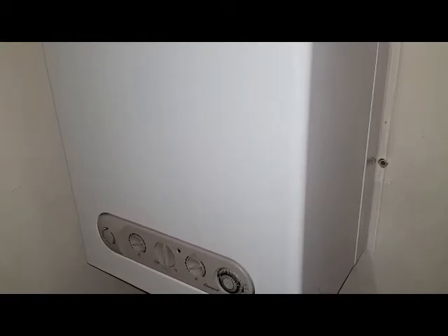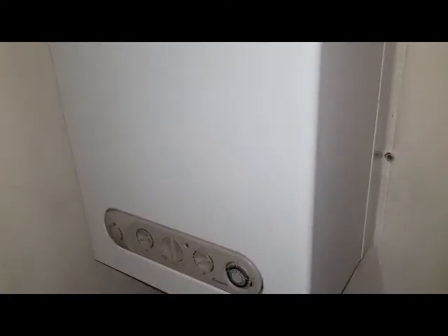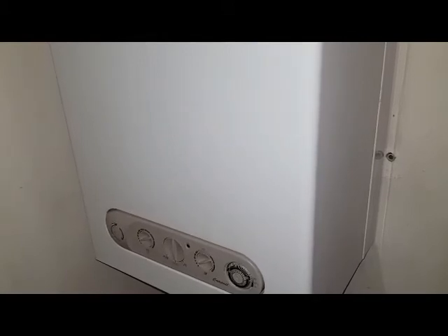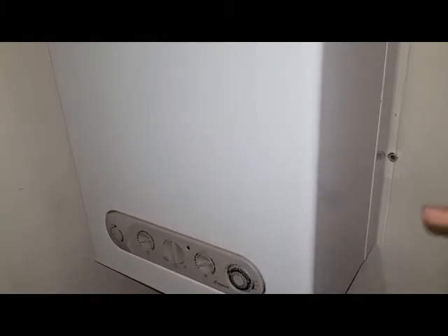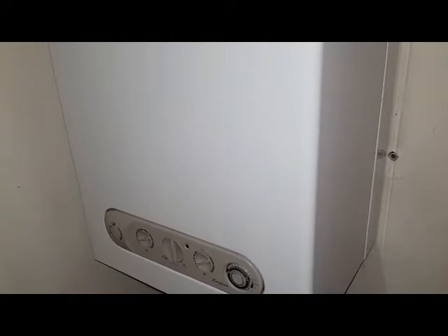You set it on a demand, the fan runs, that makes the air pressure switch. The air pressure switch sends the signal to the PCB, which sets the ignition. At the same time, the gas valve opens and the flame lights up and sends the signal back to the PCB. Everything's okay, safe to run. That's it, yeah. So that's the sequence of events.